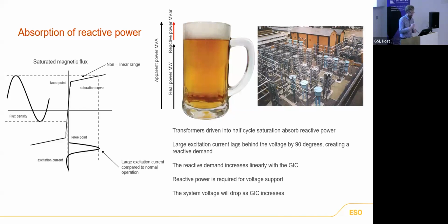So back to our chart earlier of the transformer showing the large excitation current component. And that excitation current, as I explained, was to set up the magnetic field within the transformer. So when the transformer is driven into half cycle saturation, it absorbs more reactive power than normal. The large excitation current lags behind the voltage by 90 degrees. That's just the phase angle of the currents versus the voltage. And that creates a reactive demand in that transformer. The reactive demand increases linearly with the GIC current. So the more GIC you've got from space weather effects, the higher this excitation current is going to be.